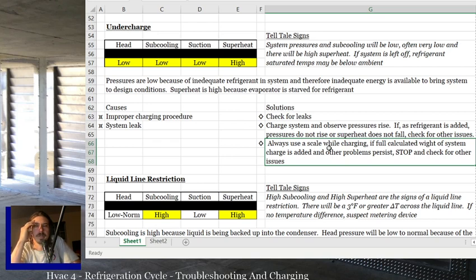One thing I didn't address, I meant to address this at the beginning, so let's talk about it now real quick. Alright, so all these are based on a fixed orifice. If you have a TXV, it's going to be the same. But the thing is, on a TXV, the TXV is going to adjust to try and fix these values. So if you've got an undercharge with a TXV, head pressure is going to be low, subcooling is going to be low, suction pressure might be low to normal, superheat will be high to normal. Everything on suction side is going to skew towards normal with the TXV.